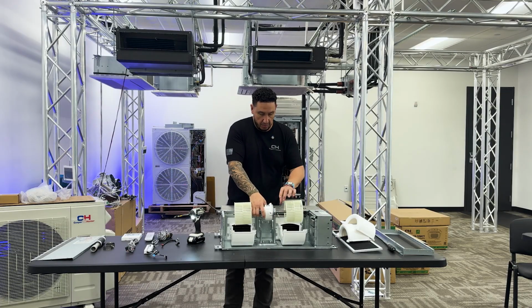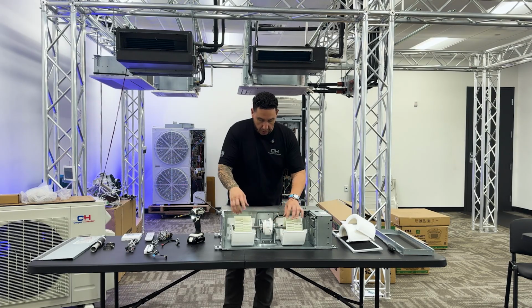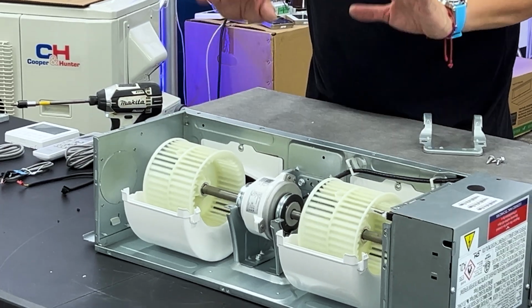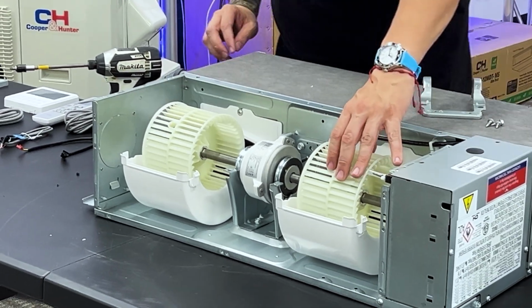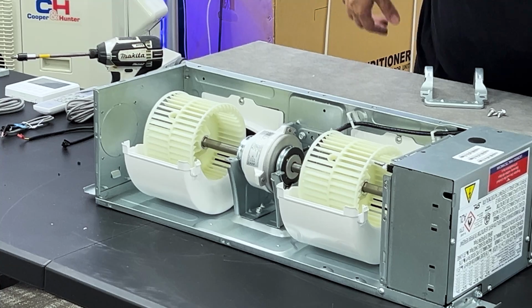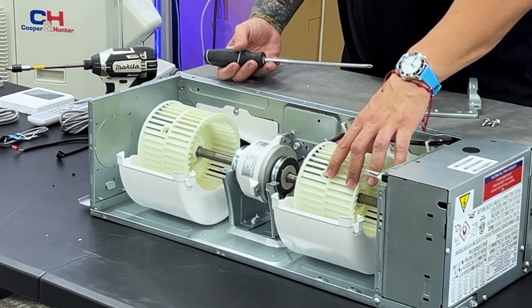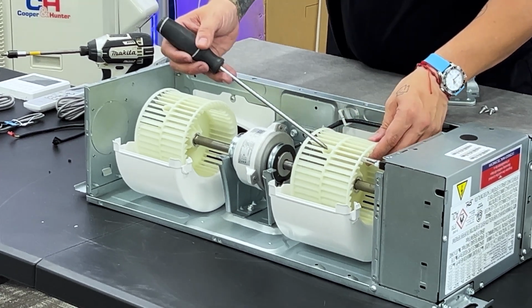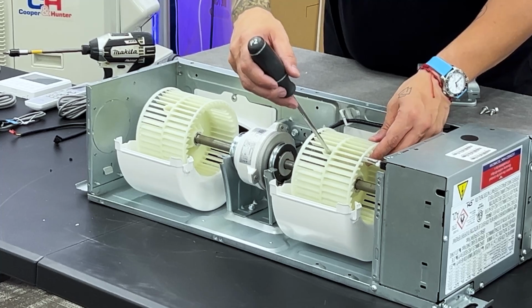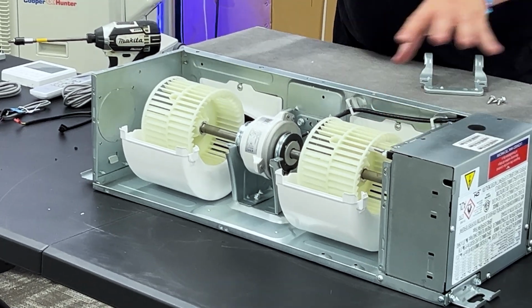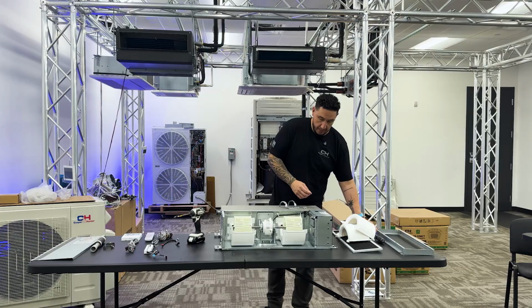I could disconnect this from the board, go ahead and take the blower wheels outside, rinse them off, let them dry, or with the long screwdriver, I could go right here into the opening notches like we have on all of our blower wheels. With my screwdriver, go inside, release the tension to remove the blower wheel completely.